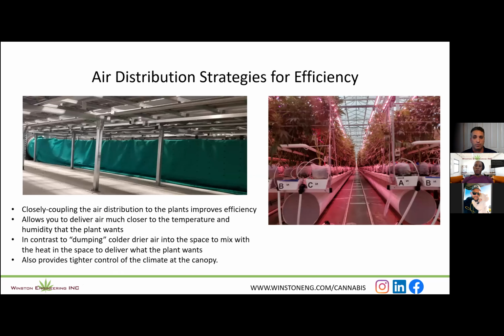All right, looking at air distribution, your ductwork system. So I'm going to tell you just kind of our philosophy at Harvest Integrated, which is we try to get that air as closely coupled to the plant as possible. If we can get that air next to the plant, we can deliver air that the plant wants, at the temperature it wants and at the humidity level it wants. If you don't put that air next to the plant, you got to mix it in the room, which means you got to send it out cool enough that it's going to mix with the heat in the space to give you the set points that you're looking for or what the plant wants.